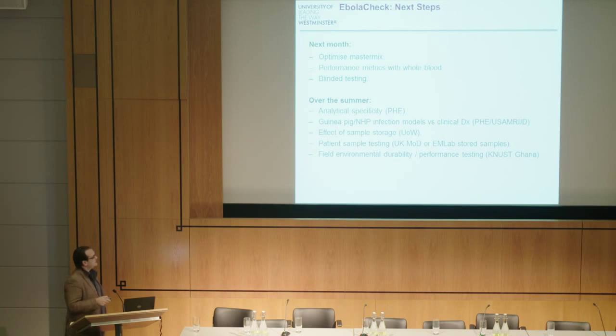And after that, we will transfer 3 instruments to the Kwame Nkrumah University of Science and Technology in Kumasi, Ghana, and they will take them out with mock samples with armored RNA to the jungle, to the seafront, to cities, to dusty places, and try and repeat the results. They will not know how much, if there are any armored RNA particles in the tubes. They will just send us back the data in a blinded fashion, and we will decode it by a third party, just as if it was a clinical trial, to see if it does what it says on the tin.